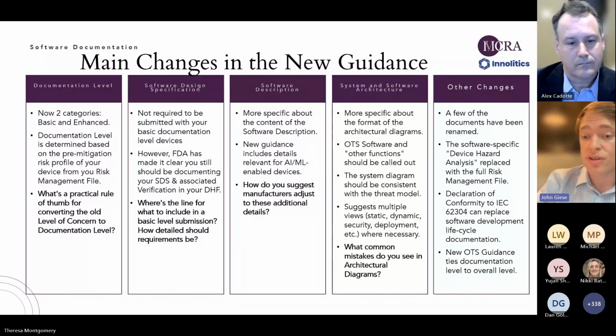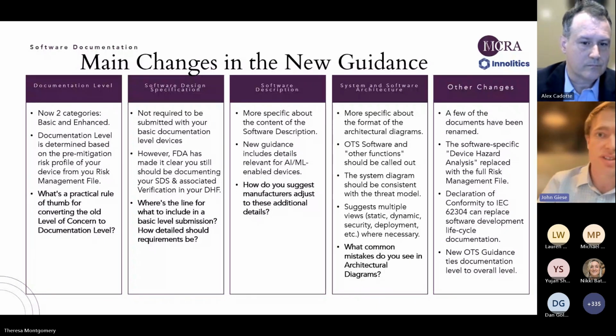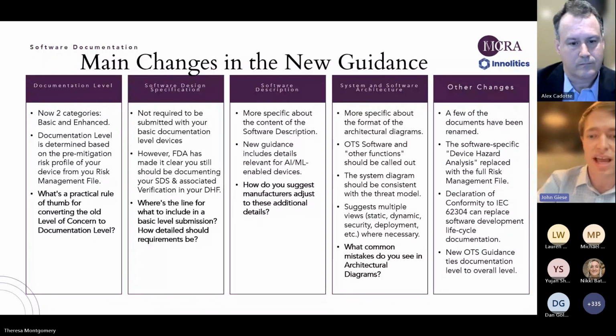Finally, you can use a declaration of conformity to IEC 62304 in place of some software lifecycle documents that you'd have to include otherwise.